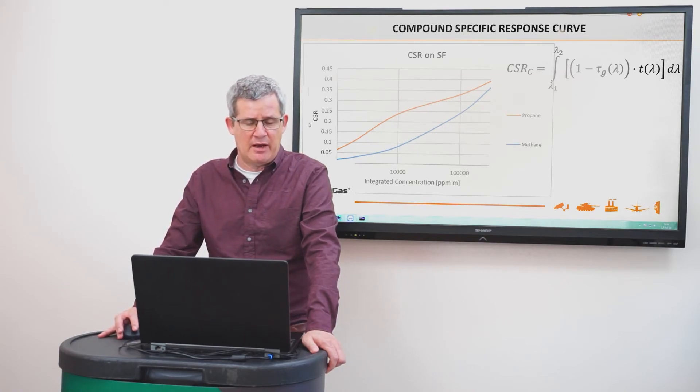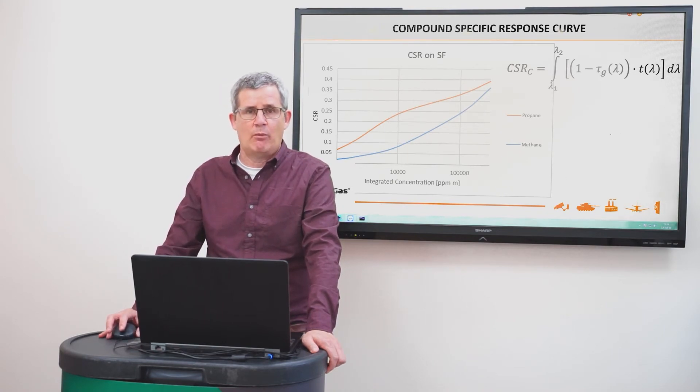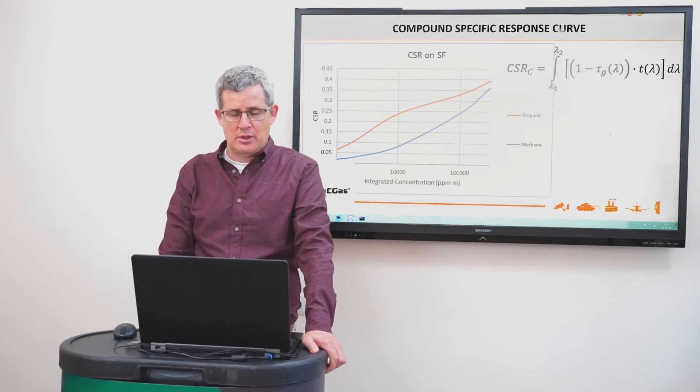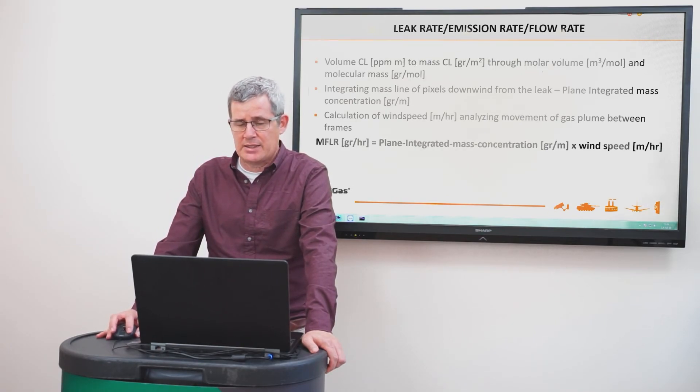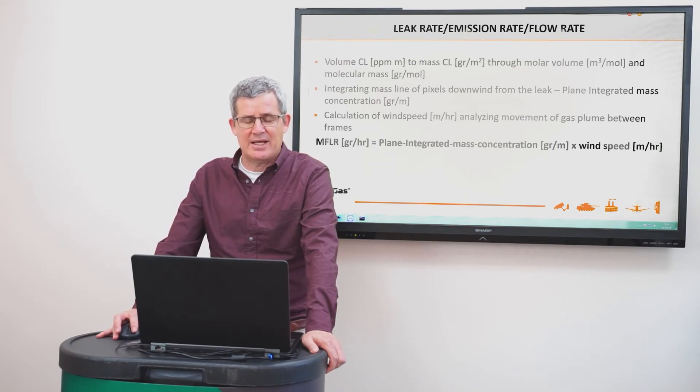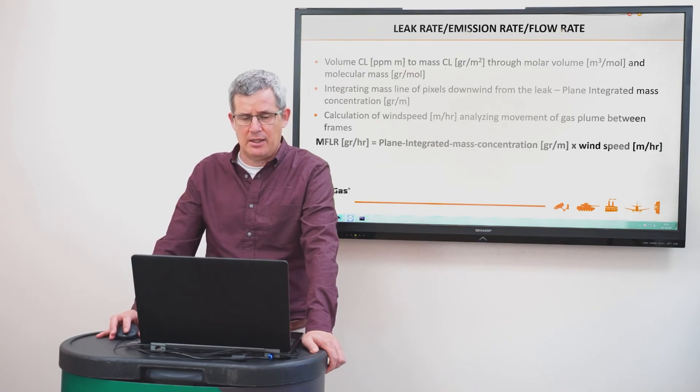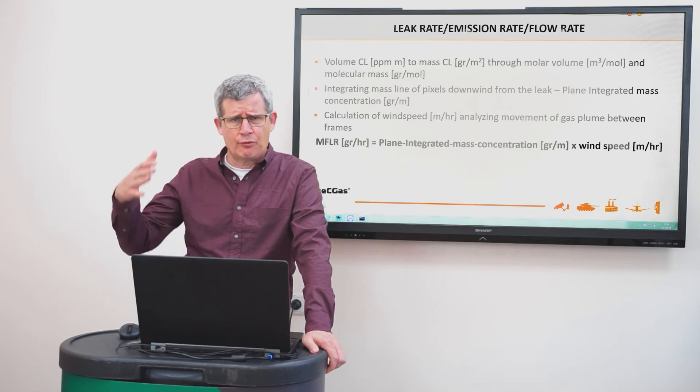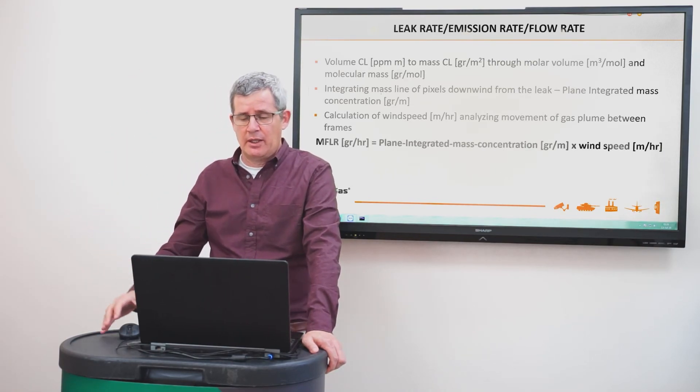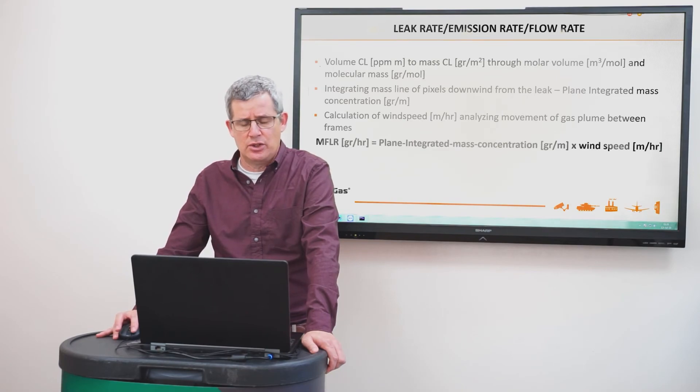Once we evaluate in every scene, the compound specific response from the camera, from the scene, we can have some way to convert this to ppm meters. So once we convert it to ppm meters, we can convert it to mass concentration through the gas density, which is taking into account the molar volume and the molecular mass of each gas. And once we have the mass concentration path lengths in gram per meter square, we can integrate this through a line of pixels downwind from the leak. And then we have the plane integrated mass concentration. And this is in units of gram per meter.